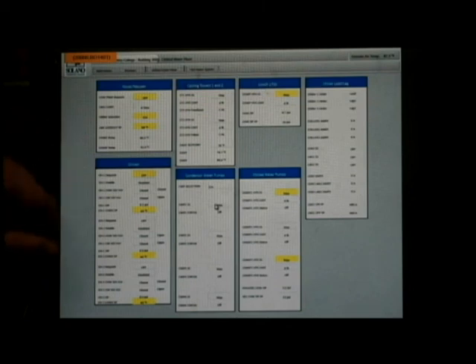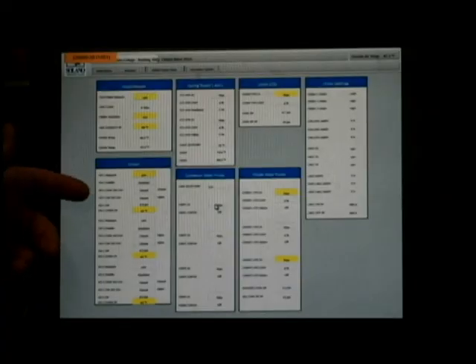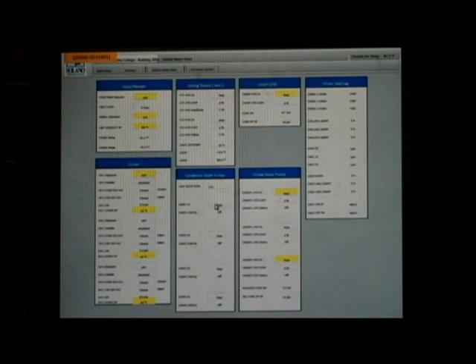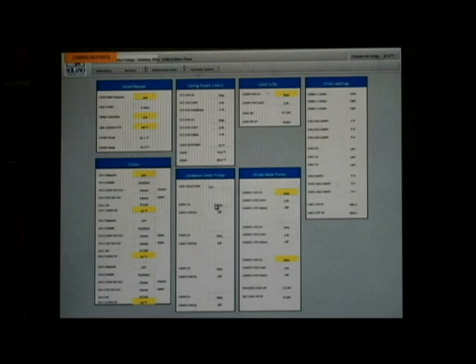So over here under the chiller side, you can see a flag for each chiller, chiller 1, 2, and 3, ones you can see a little closer. And there is a chill water request flag, which is based off of our chiller selection order, as well as a call for chilled water out in the system. Each chiller also gives us the status of the ISO valves on condenser water and chilled water side. And then we have a differential pressure on that chiller as well, so we can see how it's loading up and what's going on there. And then lastly, at the bottom of each chunk here for each chiller is the actual chilled water supply set point for that chiller. And once again, we just give that set point to each unit, and the unit does whatever it needs to and is capable of to maintain that temperature coming out.